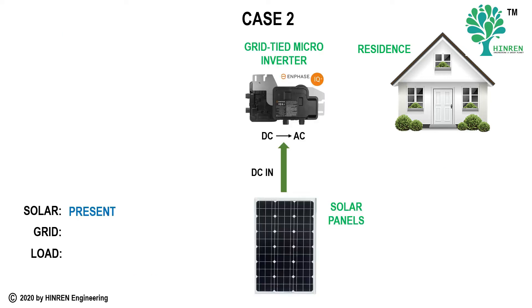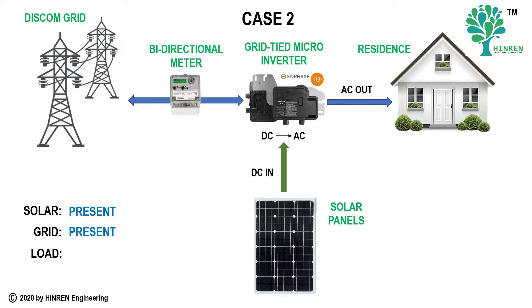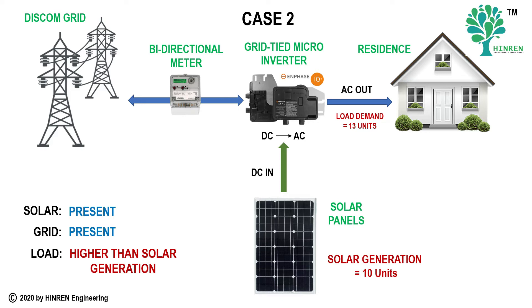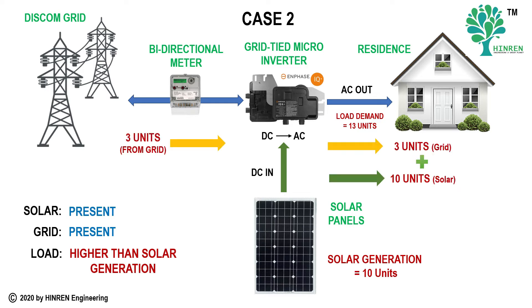In Case 2, the load demand is higher than the solar generation. Solar is generating 10 units of energy, however the load is 13 units. In this case, 10 units come from the solar panels and the remaining 3 units come from the DISCOM grid. The total demand of 13 units is met by a combination of 10 units from solar and 3 units from the power utility grid. So in this scenario, there is an import of energy from the DISCOM grid and no export.